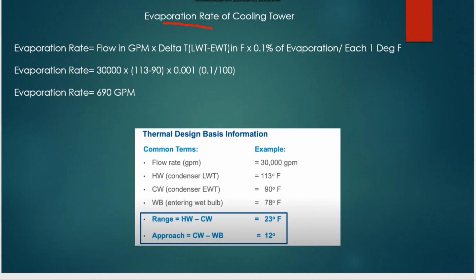The next one is the evaporation rate of the cooling tower. In the cooling tower, water evaporation takes place continuously. We can find out the evaporation rate of water by using a simple formula. Evaporation rate is equal to the flow in GPM. Here the flow rate for the chiller water flow which is coming to the cooling tower is 30,000 GPM, which I am going to consider here. And delta T is equal to the leaving water temperature minus the entering water temperature for the cooling tower. These two temperatures, the difference, we have to consider as delta T, with 0.1% of evaporation for each 1 degree Fahrenheit. Here the difference is 23 degrees Fahrenheit. For each 1 degree Fahrenheit we consider 0.1% as the evaporation rate.